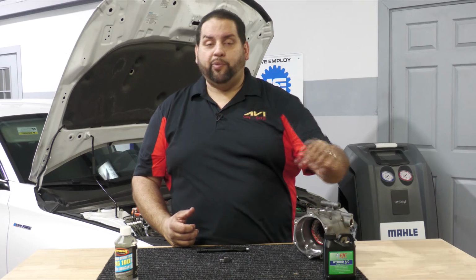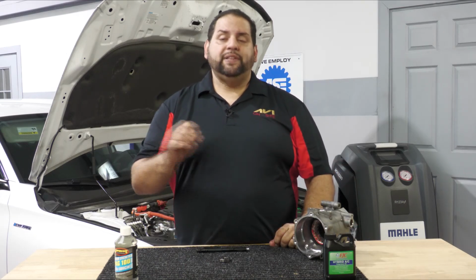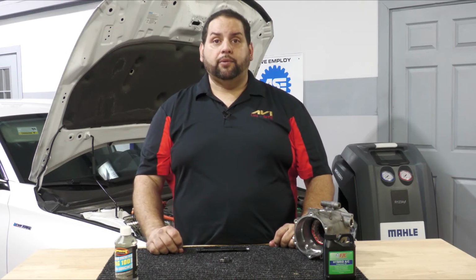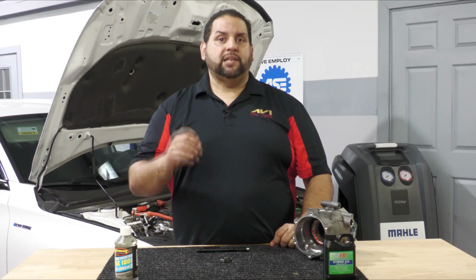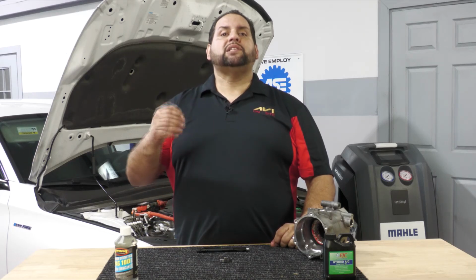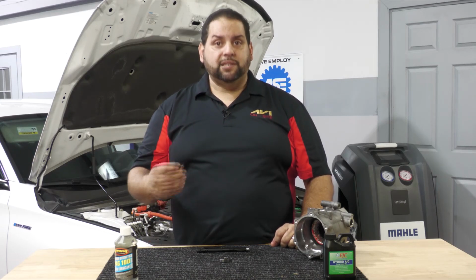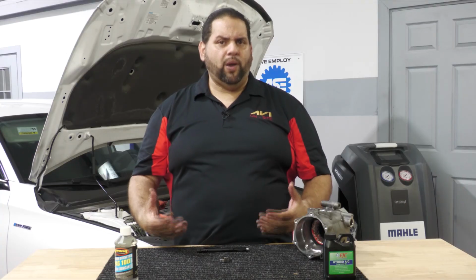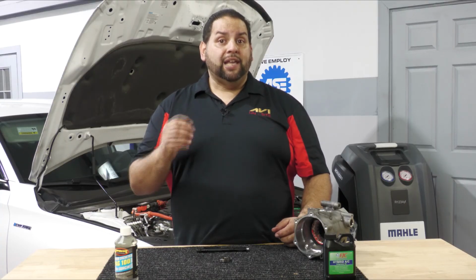Why is that so important? Well, real simple - the one thing that changes on those oils is that they're less conductive. They have more insulation properties. That's the main deal. Now why does that matter, and why do I want more insulation properties in refrigerant oil for an AC system?